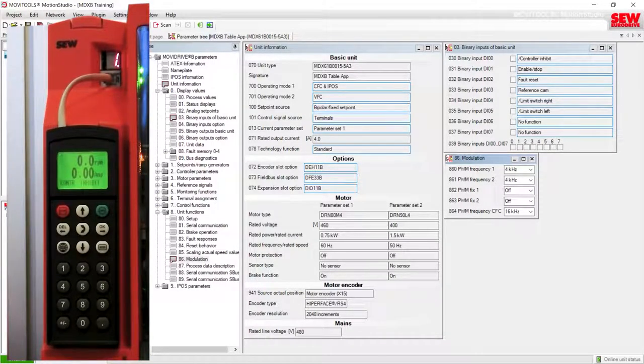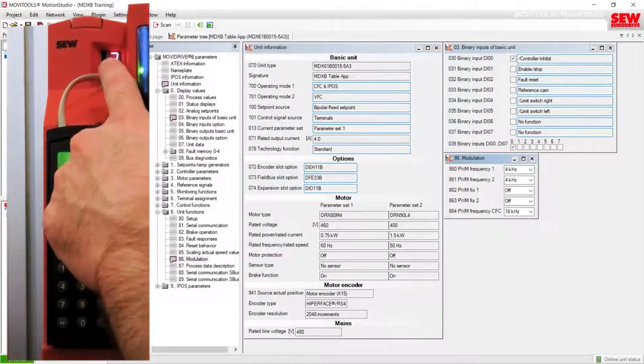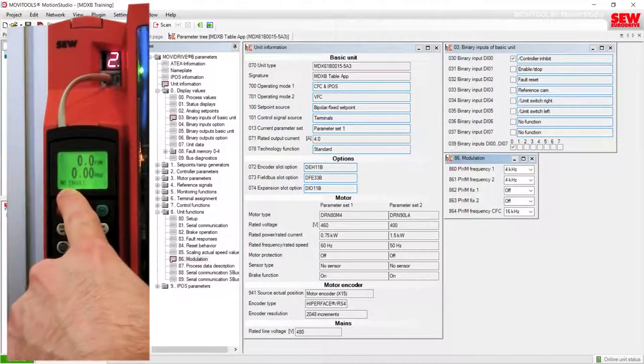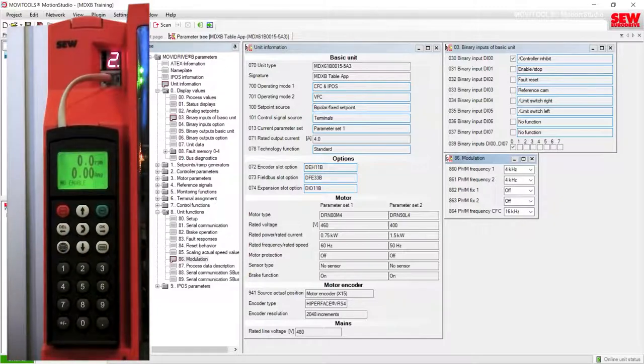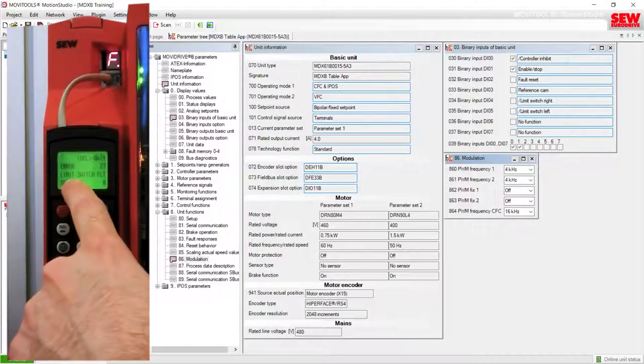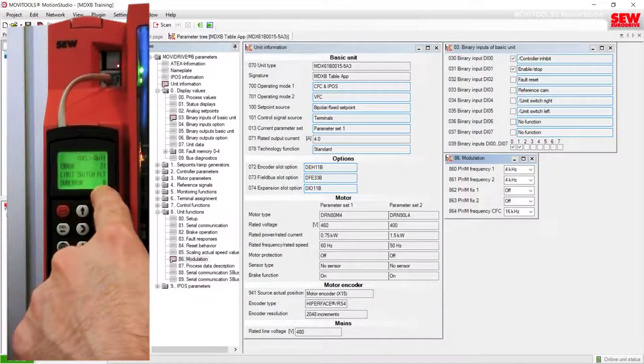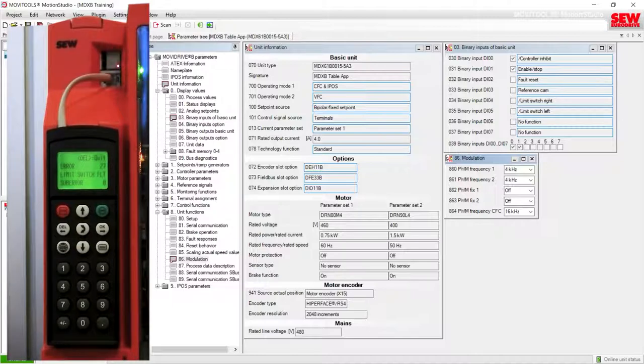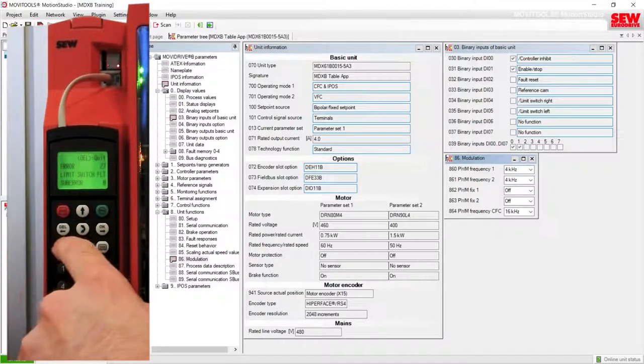Next I want to demonstrate what happens when the MOVIDRIVE issues a fault condition. Since we're still using the same application module from the last lab activity, we can easily create a fault by enabling the MOVIDRIVE without the hardware limits activated. Let's clear the controller inhibit by turning on DI00. The MOVIDRIVE now shows a number 2 status, meaning no enable. If we now give the enable signal without the limit switches turned on, we immediately cause a fault — it is currently flashing F27. Below, we can see error number 27 with a description of a limit switch fault, and sub error zero.